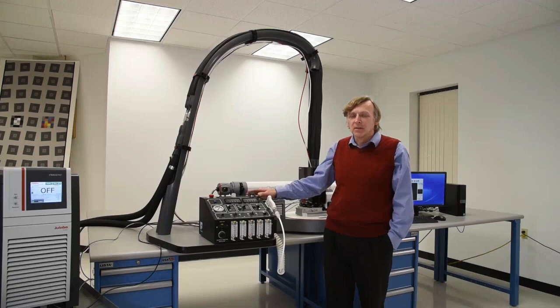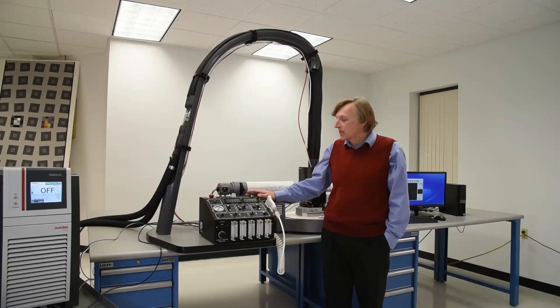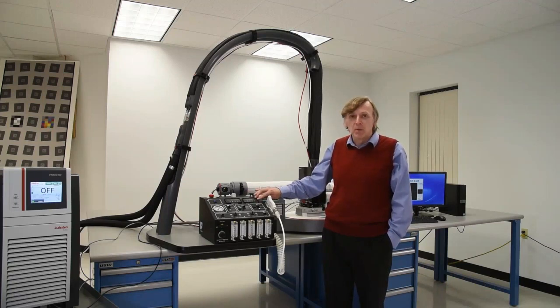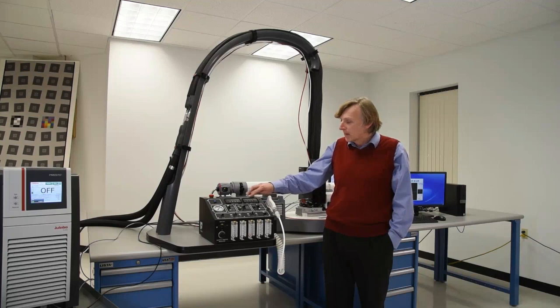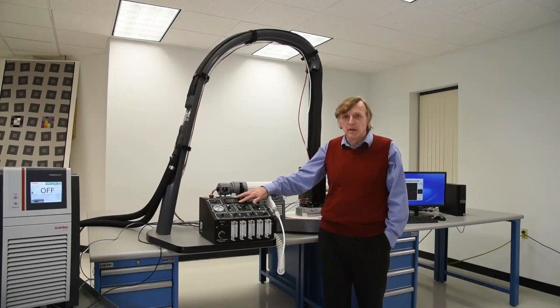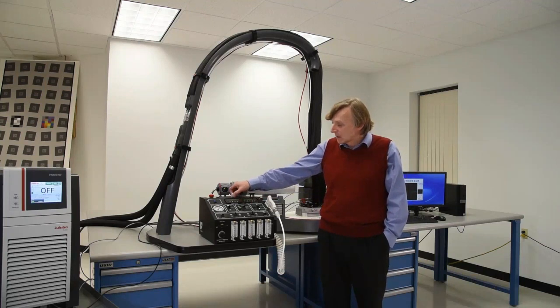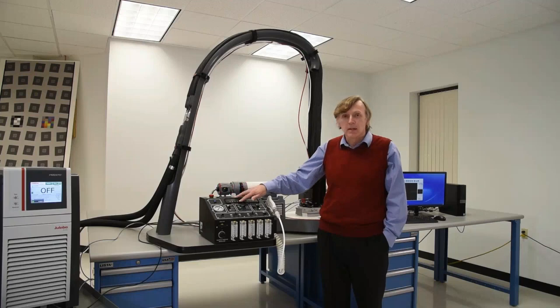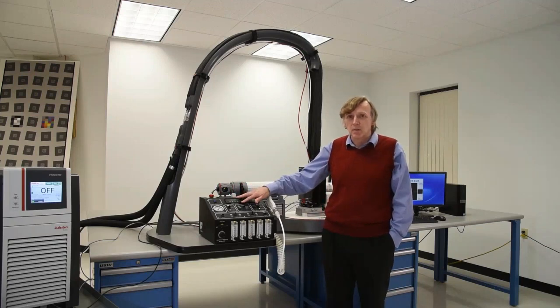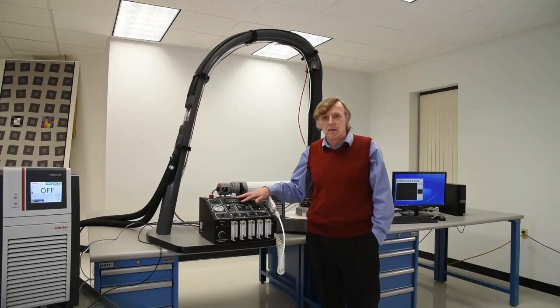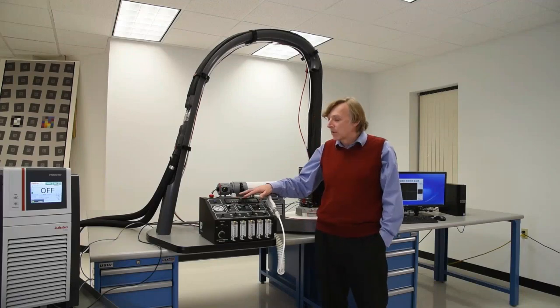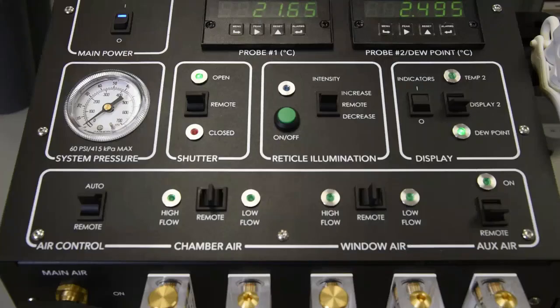The control manifold also performs a few other functions. It measures and reports the ambient dew point. It measures the temperature of the lens under test. You see here where that probe connects. It controls the mechanical shutter in the thermal chamber, as well as the internal illumination. All of these functions are controlled remotely by the Optikos 7 software, but they are also manually controllable from the front panel.